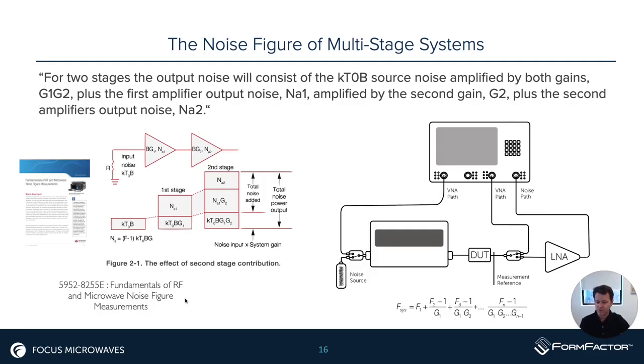Before we get into that, one application note we strongly recommend is this one from Keysight. This is an application note that's been around for years, even in the Hewlett-Packard days, and basically evolved with the new instrumentation. Very useful information in there. I refer to it in the best practices as well. In here, it discusses how the multi-stage noise figure contribution of the different stages impacts the performance and the measurement.